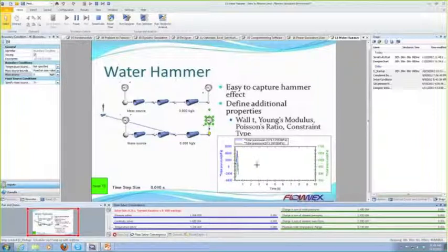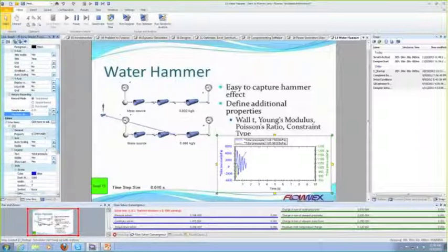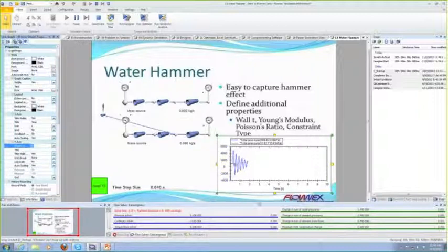we see this blue. The blue represents that initial one, so that's the network that is not protected. And then we have this other line, the green line, if you can see. The important thing is it looks like it's actually spiking, but let's look at the y-axis here. We see that we're not going from 5,000 to minus 5,000. So what I can do is come over here and specify that I do not want multiple y-axes. And so when I plot these both on the same scale, you see that my accumulator is effectively preventing these huge negative pressure spikes, which would be damaging to the system.